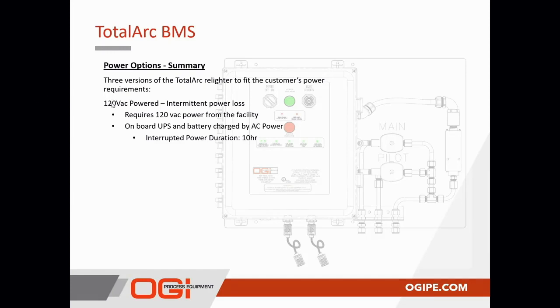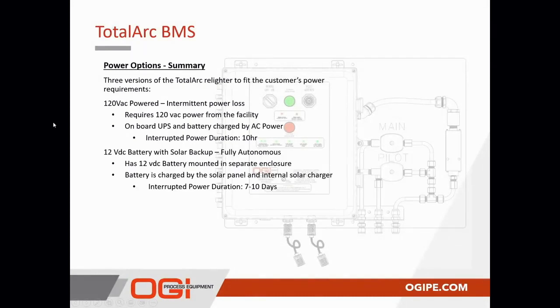The 12 volt DC battery system with solar backup is fully autonomous. We have quite a few of these in the field, and they really hold up well in all environments we've been exposed to. It has its own 12 volt DC battery mounted in a separate enclosure. It has its own battery charger that's supported by a solar panel, and it has that internal charger inside the actual battery enclosure. And in this case, as we discussed, it has 7 to 10 days worth of autonomous operation in the event that you lose the solar panel.